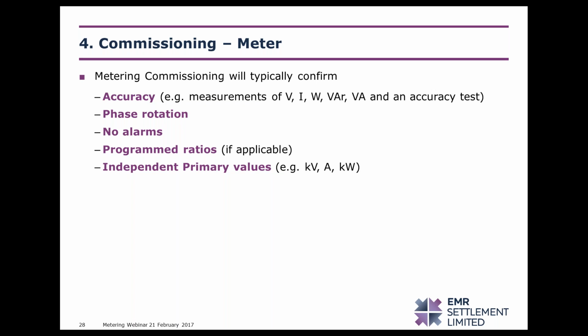One technique to be able to do that is to measure the secondary values for the voltage and current coming into the meter and comparing that with the converted primary values in the meter. So for example, if you had a 200 to 5 amp CT ratio and you measured 5 amps on the secondary terminals coming into the meter, you would expect the meter to have converted that to a primary value of 200 amps. It is always useful to compare the meter commissioning with an independent metering system. So if there's any independent instrumentation in the substation, that should be included here as an extra validation check that the meter is recording energy correctly.